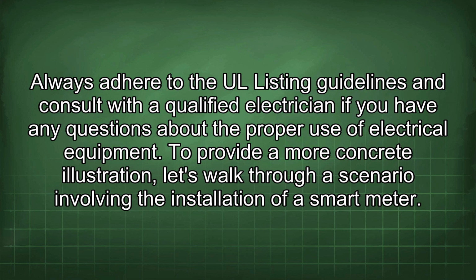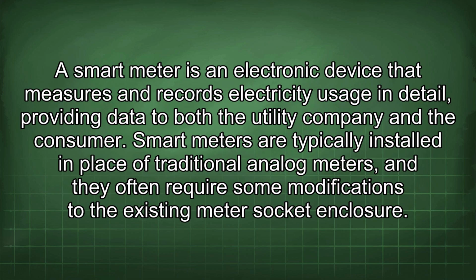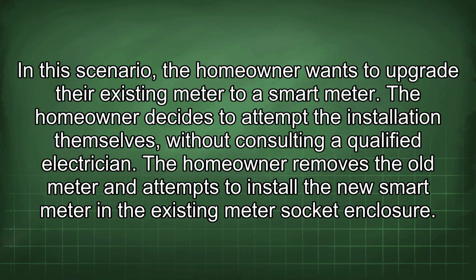To provide a more concrete illustration, let's walk through a scenario involving the installation of a smart meter. A smart meter is an electronic device that measures and records electricity usage in detail, providing data to both the utility company and the consumer. Smart meters are typically installed in place of traditional analog meters, and they often require some modifications to the existing meter socket enclosure. In this scenario, the homeowner wants to upgrade their existing meter to a smart meter.